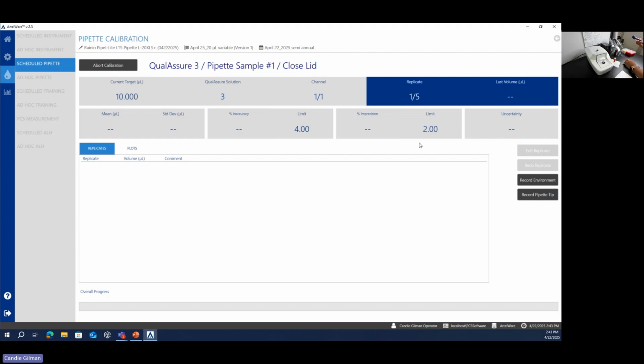And I'll grab my pipette, place a tip on it. I'm just going to adjust my pipette volume down to 10 microliters real quick here. Alrighty, so now we're going to get started. I'm just going to pre-wet my pipette a few times before I get started. And I'm going to make my first dispense into the instrument. And after I make my dispense, I'm going to close the lid, and the vortexer is going to vortex and mix that blue dye in that vial with the red dye that I just dispensed. And here's my first volume, 9.827.